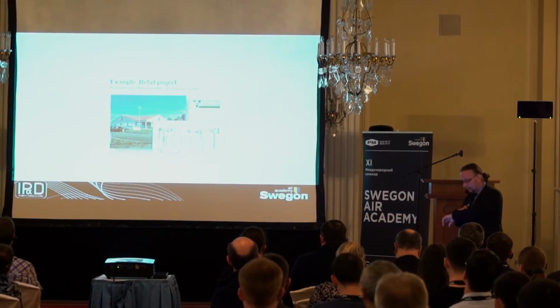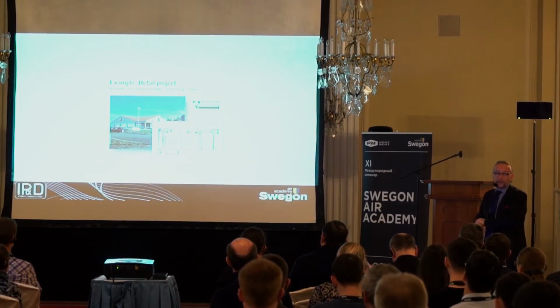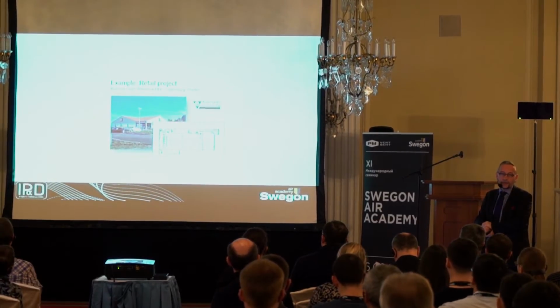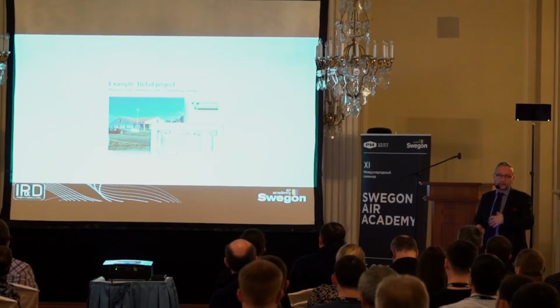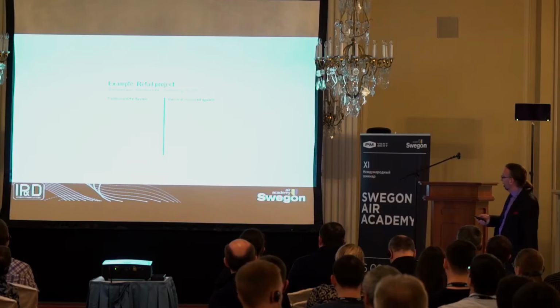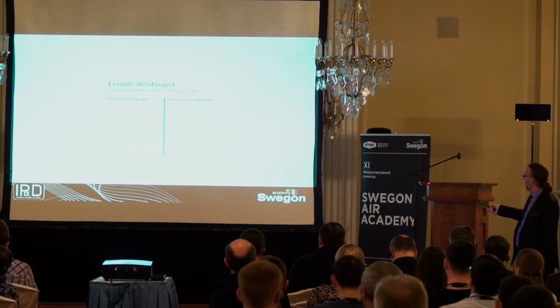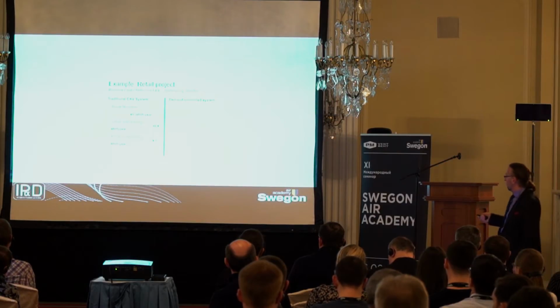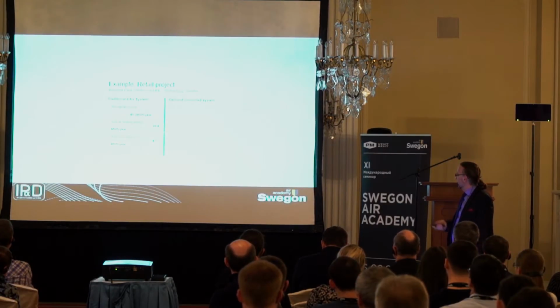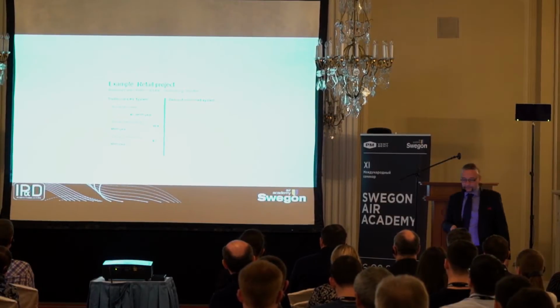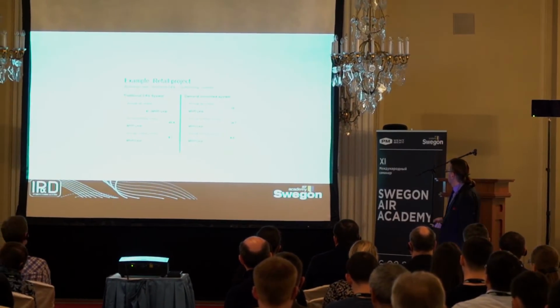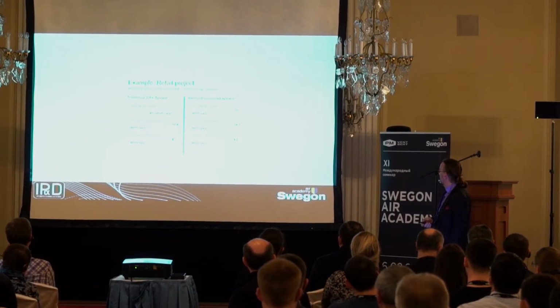I want to close off giving you some examples. It is a retail project, how to save money on that. We built over 100 little shops in making it as efficient as possible. This is standard retail. And we compare traditional constant air volume system with a demand-controlled system, where everything is demand-controlled. And as you see, the fan power per year will be 41 megawatt hours in a traditional system. And then the heating, 46 megawatt per year, and cooling about 10. Well, in the demand-controlled balanced system, you see the fan power goes down to basically 10 megawatt per year. That's 4 times less. While the heating is about half, and cooling is roughly the same.